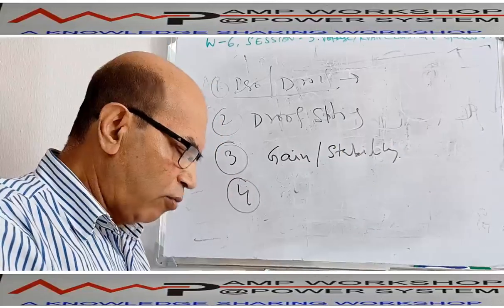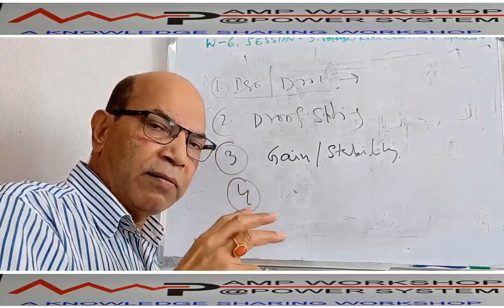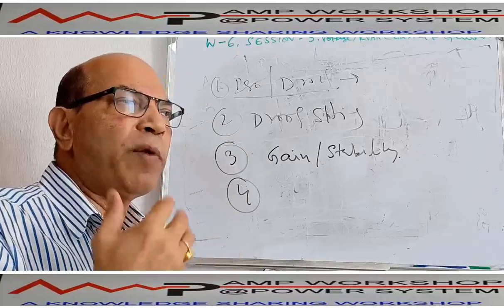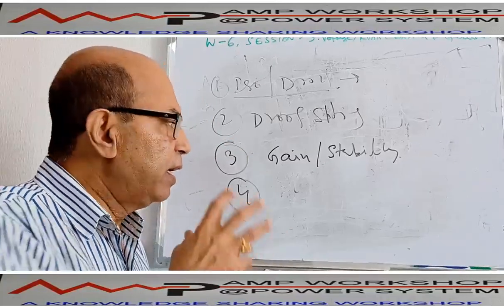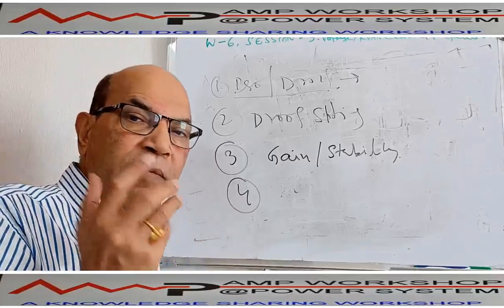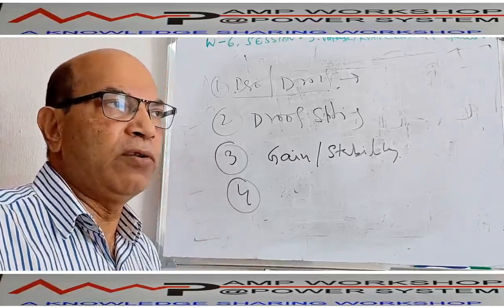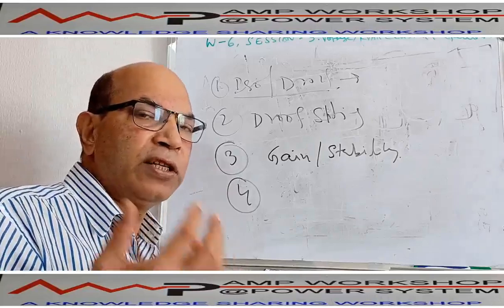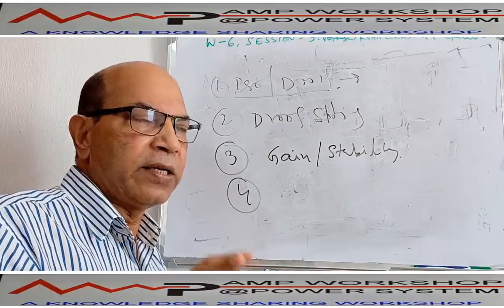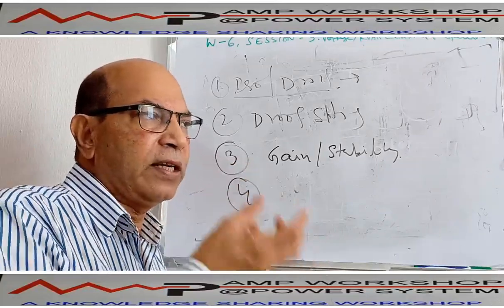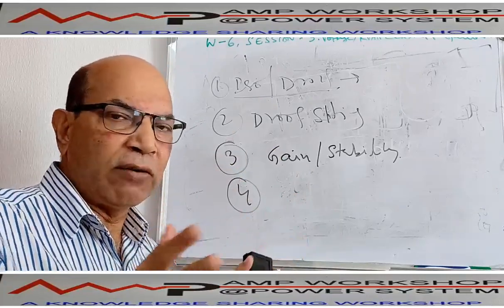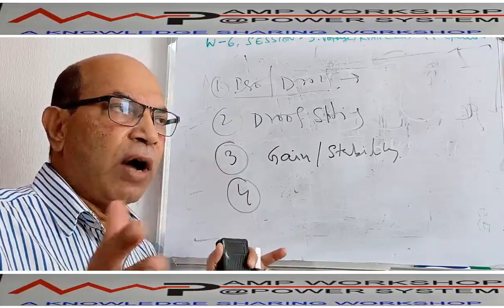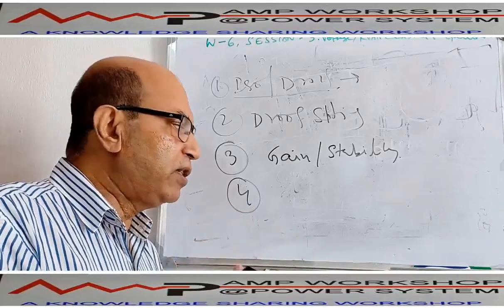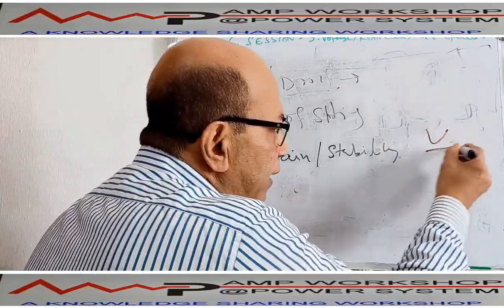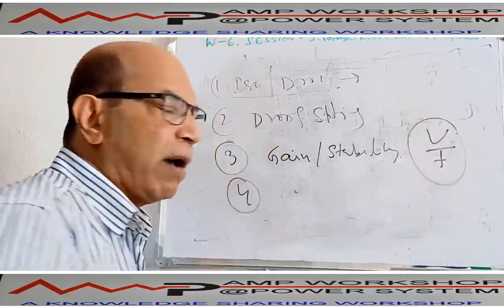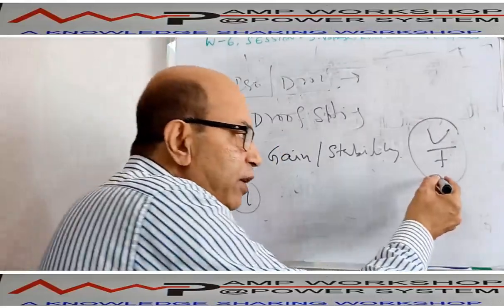Number four, in the case of governor or speed control, an over speed, under speed switch is there. In the case of AVR also, there is an under voltage switch. Why is it important? Under voltage condition arises because there are two different aspects here. One device is producing voltage, another device is producing frequency. So these are not related to each other. They are independent. So how they are controlled, we don't know. That's why this generator always controls V by F. It's maintained V by F. This is to be maintained to avoid core saturation. V by F ratio is to be maintained.